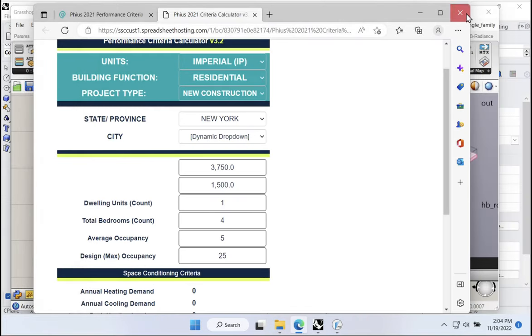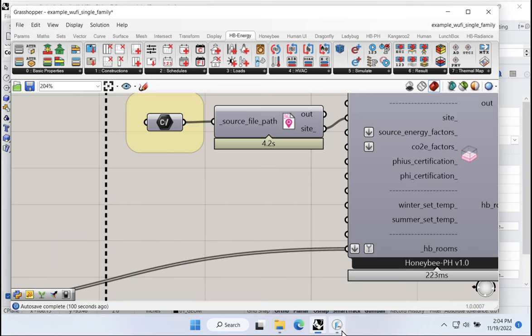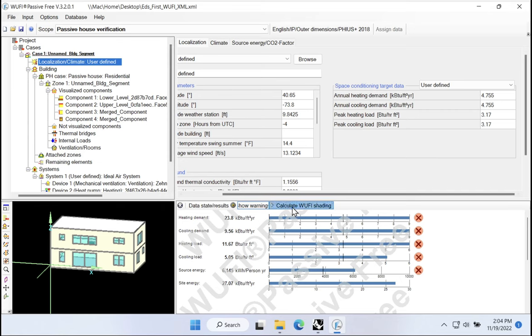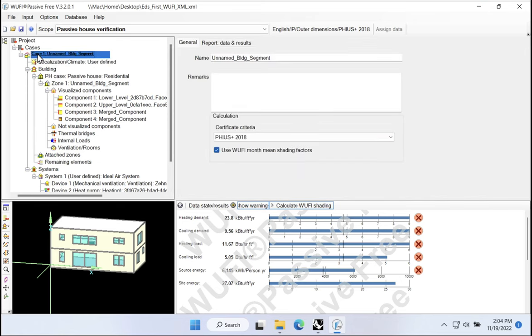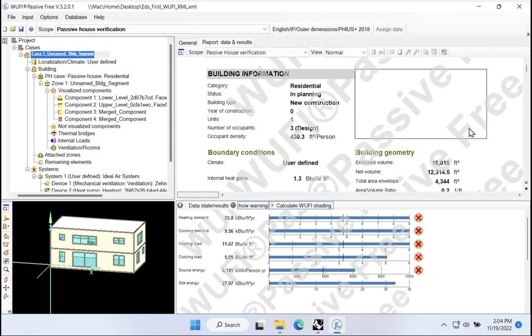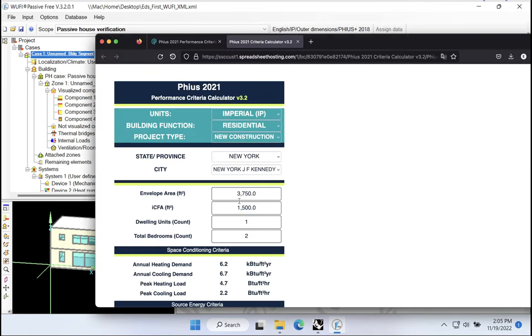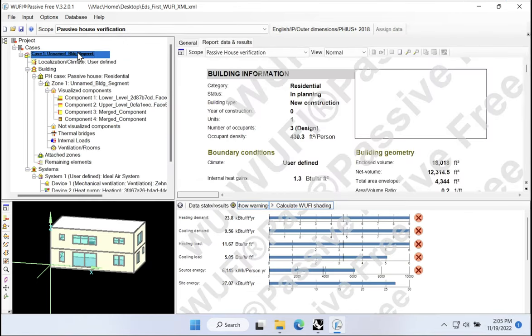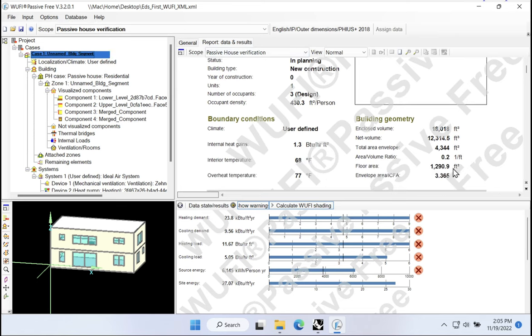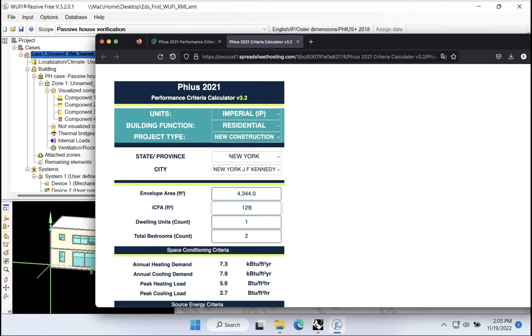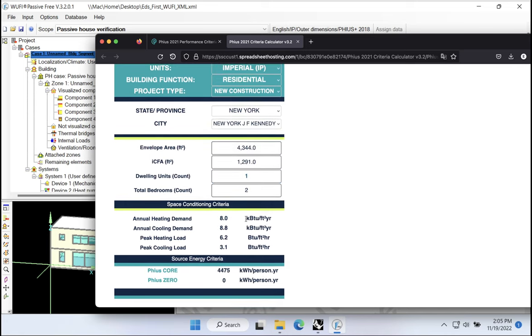I'll go back to WUFI. The easiest place to find this information, once everything is calculated and running properly, is to come up to case number one and go to report. You'll find the data you want right here: enclosed volume, net volume, total envelope area of 4,344, and total floor area of 1,291. So total envelope area is 4,344 — we enter that. And then ICFA, going back up to the case report, floor area is 1,291. Let's say 1,291. And notice down here that our targets were moving around as we adjusted those values. Here are our final targets.